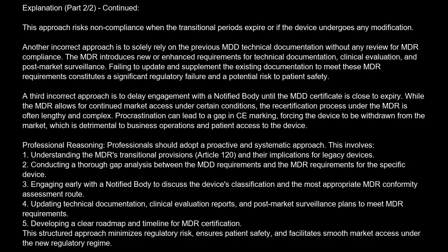Failing to update and supplement the existing documentation to meet these MDR requirements constitutes a significant regulatory failure and a potential risk to patient safety. A third incorrect approach is to delay engagement with a notified body until the MDD certificate is close to expiry. While the MDR allows for continued market access under certain conditions, the recertification process under the MDR is often lengthy and complex. Procrastination can lead to a gap in CE marking, forcing the device to be withdrawn from the market, which is detrimental to business operations and patient access to the device.